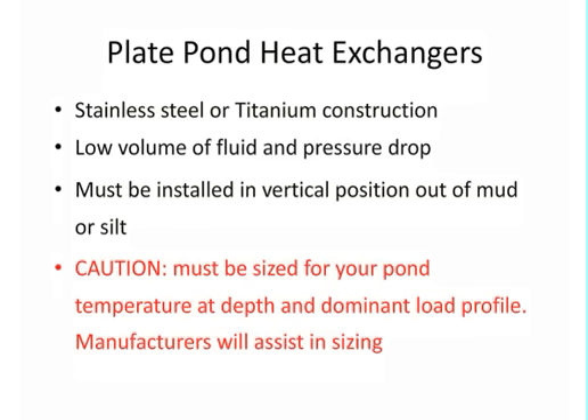So we're going to change up to plate-style pond heat exchangers. Plate as in, you're going to see some examples in just a moment here, stainless steel or titanium. Stainless steel is typically what is used. However, the manufacturers I'm aware of also manufacture titanium plate construction heat exchangers. When would you use titanium? Well, titanium would be in a very brackish or aggressive water, and or some saltwater applications.